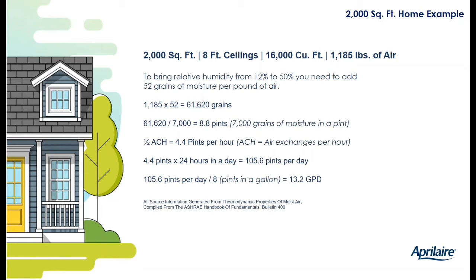So we have to add 8.8 pints. But the house isn't a Tupperware container. It's got some air changes. In this case, we're going to assume half an air change. So 4.4 pints per hour. So what we have to add each and every hour, multiplied by 24, is 105 pints per day. 8 pints in a gallon, so 13.2 gallons per day is what this house needs to go from 12% to 50%. And that's once it's in a steady state.